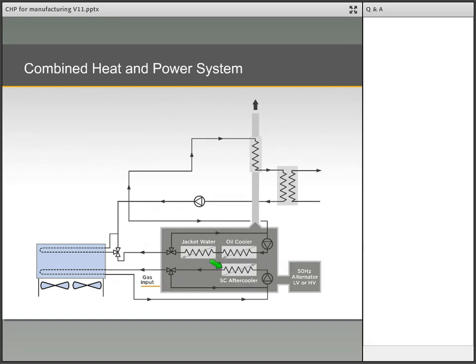A separate circuit aftercooler, or secondary cooler, also known as an intercooler circuit, comprises a pump, a three-way valve, and the intercooler itself, which is a heat exchanger in which the gas and air mixture, compressed and heated by the turbocharger, is cooled before it enters the engine.